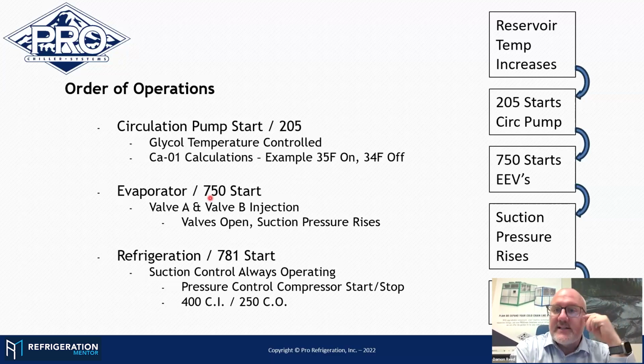But if I'm watching a system, a common call I might hear is that the compressor's not starting. Okay, are there any active alarms? No. Okay, what's your suction pressure? 350. Well, why is our suction pressure only 350? I don't know. Well, let's backtrack in the circuit. What's our flash tank doing? What's our flash gas bypass valve doing? What are our 750s doing? Are our valves even open? What is the temperature of the fluid running through my evaporator? Is it a lot colder than I think it is? Those are the things you start to drill down on once you've got this.